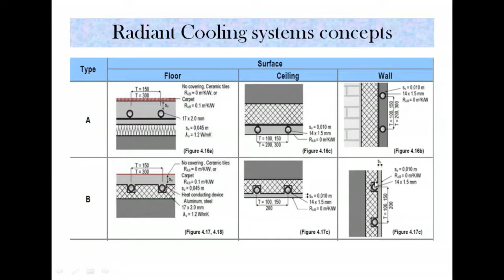Same thing could be applied to a wall. This is the wall. You make an insulation on that, and on that wall you put the panels. Ready-made panels are available, which you stick on, and the pipes are already arranged on that panel. PEX pipes or copper pipes are available, with ready-made tunnels through which the water is circulated, and it creates a cold surface on the wall. Now if you don't have sufficient space above the slab, then you can recess the insulation and install the pipe like this. Same way for the ceiling.